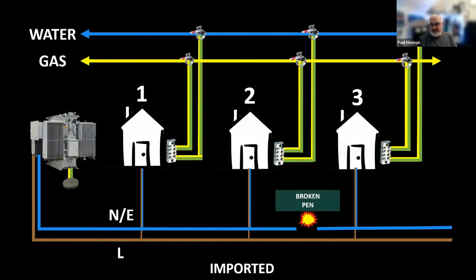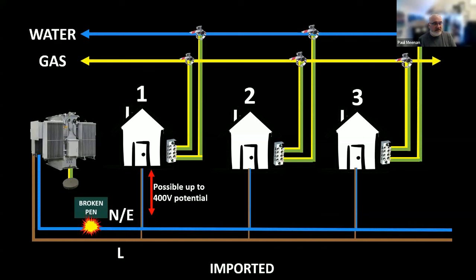And eventually, I've always said that when you've got energy that shouldn't be there on your earthing system, that's a precursor to a failed neutral in the supply network. So it's one of the things that we look out for, and we call it a broken PEN. And the reason why is I'll show you in a second. Now, what that leads to is, if we do have a broken PEN, you could get potentially 230 volts in house three with step or touch potential. So you could go outside, touch your tap and have 230 volts. Further down the line, if you have a broken PEN where you've got multiple houses across phases, you could have 400 volts, which could lead to great injury. And also, if you get 400 volts, you could find your televisions and all your electronics blowing up or failing. So that's as simple as it gets.